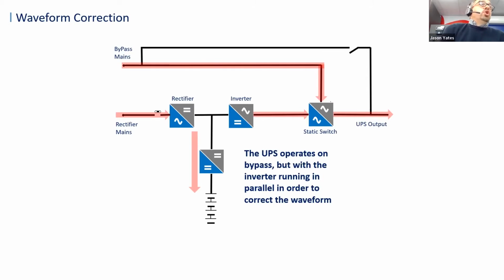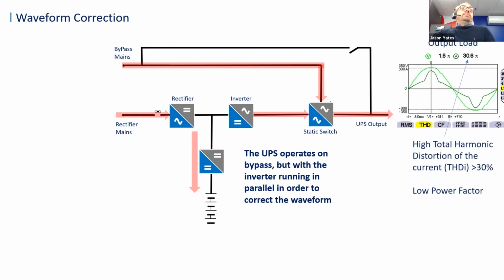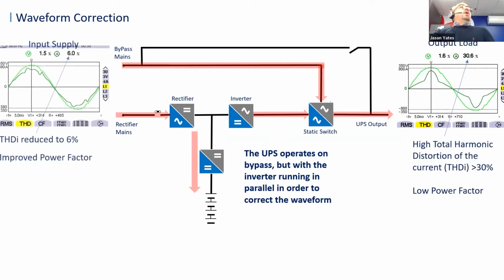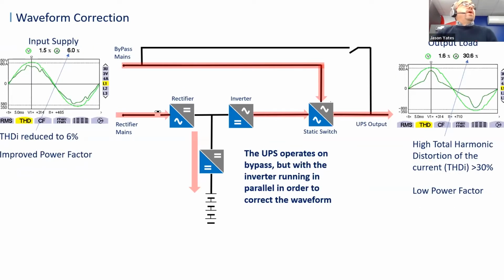Now, in this mode of operation, the UPS operates on bypass, but the inverter is running, and the inverter is actually operating in parallel with the bypass in order to correct the waveform being applied to the incomer. So, for example, if we applied a load to the output of the system, these are only representative figures, in this case it has a high total harmonic distortion of the current, THDI, of greater than 30%, with a low power factor. Because of the way the active power waveform corrector works, the system now corrects that waveform. As you can see, it has reduced that down to around 6%, and obviously improved the overall power factor. Now, in reality, the performance of the system will change depending on exactly what we're supplying and exactly what tolerance it needs to meet.